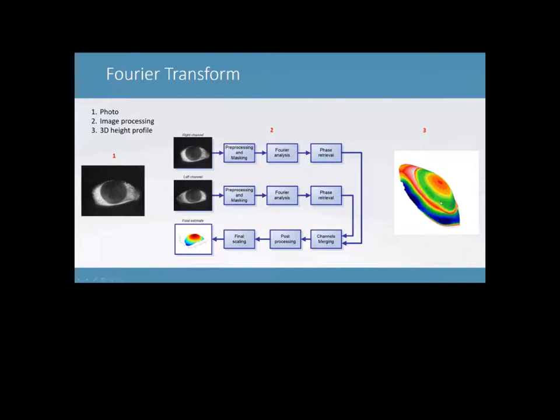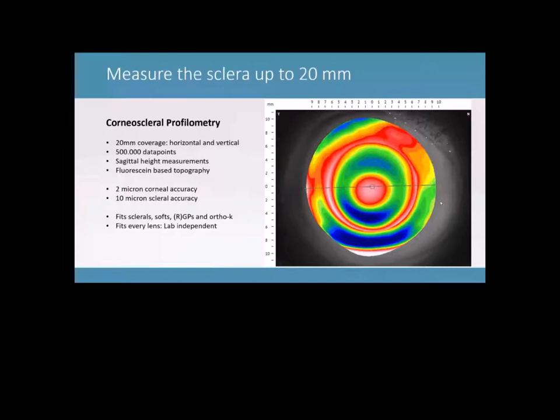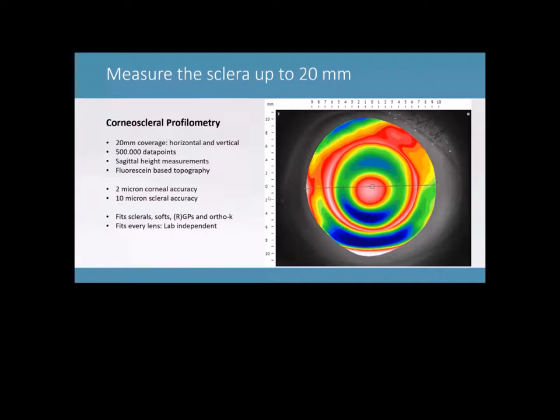So what can we do with this information? We're able to measure up 20 mm of the eye horizontal and vertically, as you can see up here, which contains about half a million data points. So like I said, we directly measure sagittal height and the topography image is based on fluorescein that you put into the eye. If you compare this directly to a topographer such as a Medmont, the accuracy of the corneal area is very high. So it's very comparable. We have about a 2 micron accuracy of the cornea and we've got about a 10 micron accuracy on the scleral part.